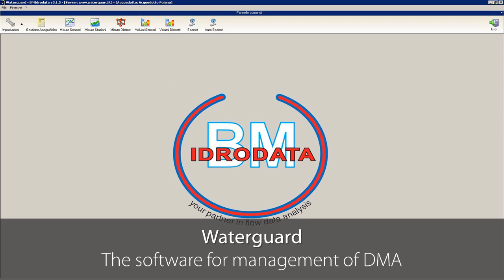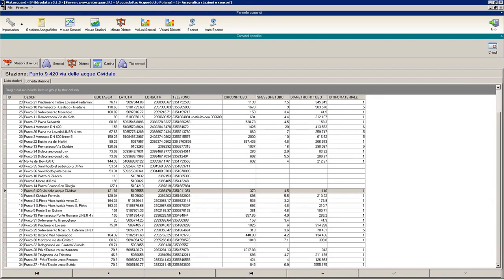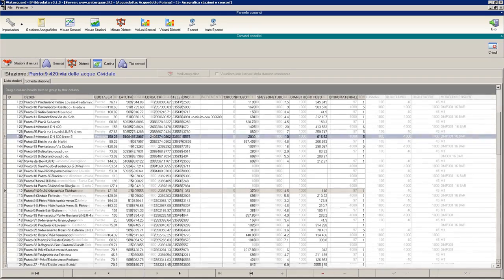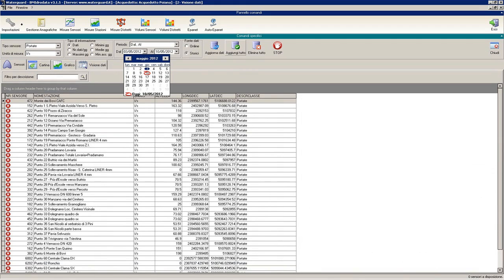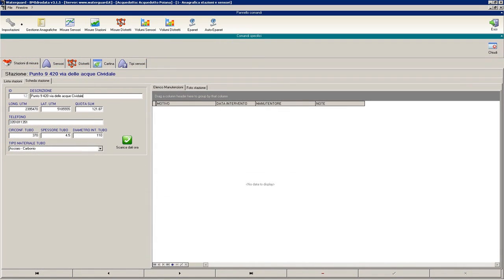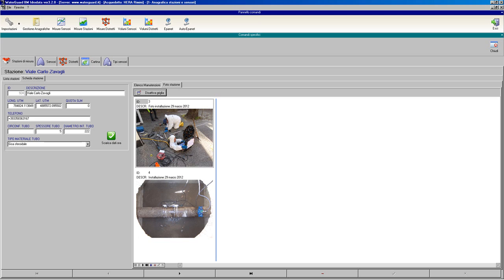The software receives incoming data via GSM/GPRS systems. After checking and validating the records, it analyzes them automatically in order to quantify the average consumption of the DMA, the water losses trend, and any possible malfunction. WaterGuard allows you to manage all measuring sites' data together and simultaneously, and it registers maintenance procedures carried out in an internal database. It is possible to define a specific set of parameters for each measuring site in order to apply automatic filters and algorithms necessary for data analysis and understanding.